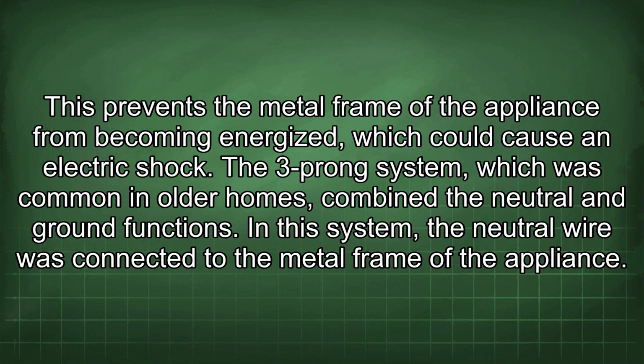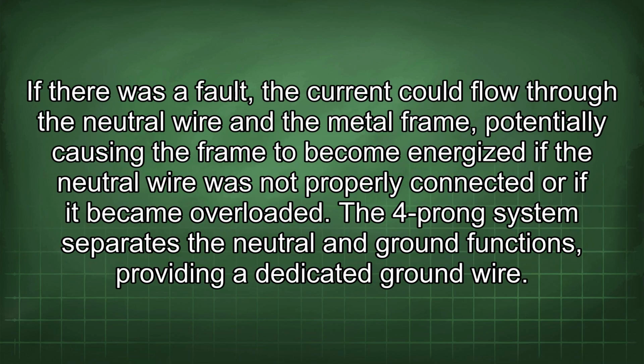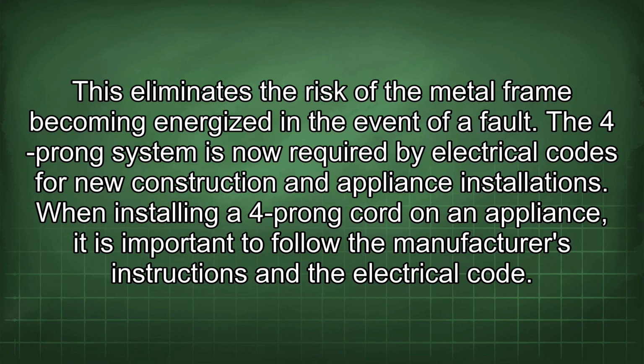The 3-prong system, which was common in older homes, combined the neutral and ground functions. In this system, the neutral wire was connected to the metal frame of the appliance. If there was a fault, the current could flow through the neutral wire and the metal frame, potentially causing the frame to become energized if the neutral wire was not properly connected or if it became overloaded. The 4-prong system separates the neutral and ground functions, providing a dedicated ground wire. This eliminates the risk of the metal frame becoming energized in the event of a fault. The 4-prong system is now required by electrical codes for new construction and appliance installations.